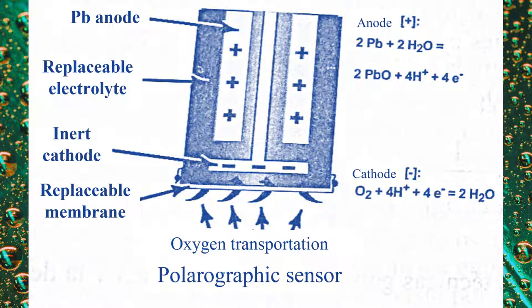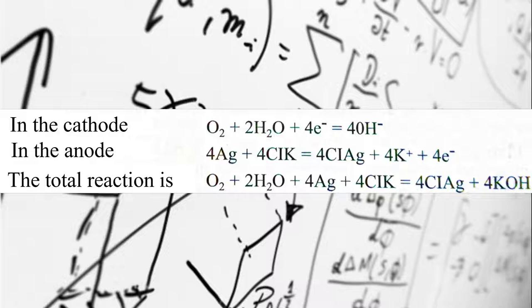The chemical reactions that take place are the ones you can see on the screen. Since for each oxygen molecule that is reduced, four electrons enter the cell and four leave the anode, an electrical current is obtained from cathode to anode that is directly proportional to the amount of oxygen that passed through the membrane.